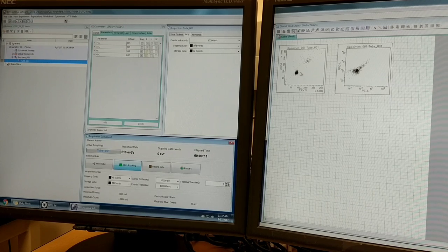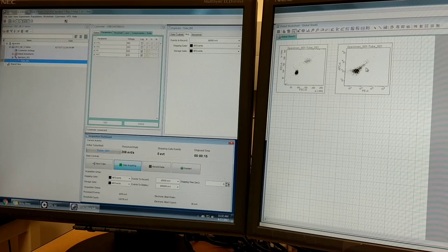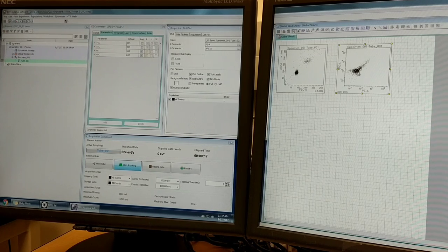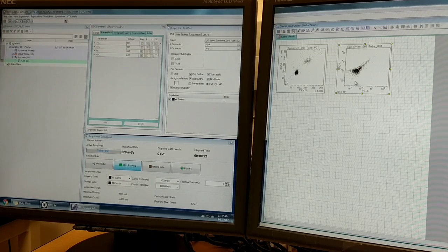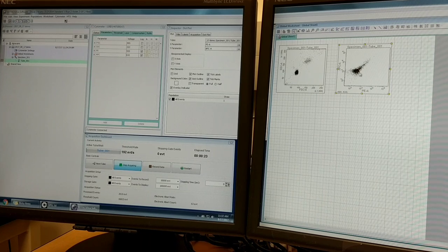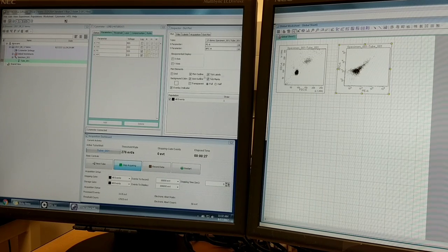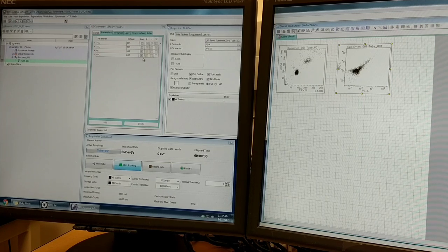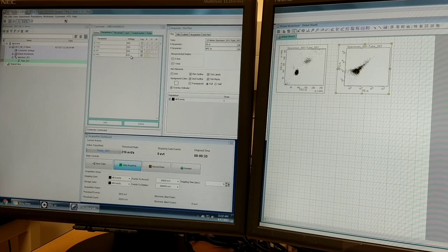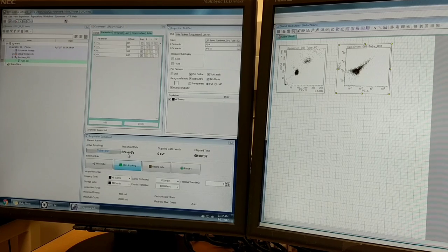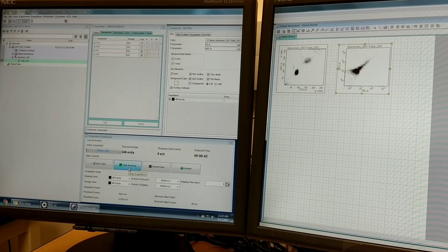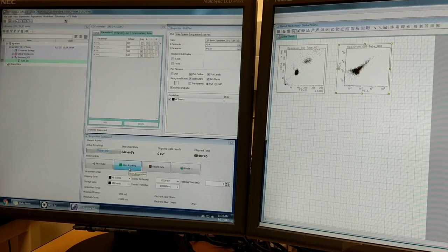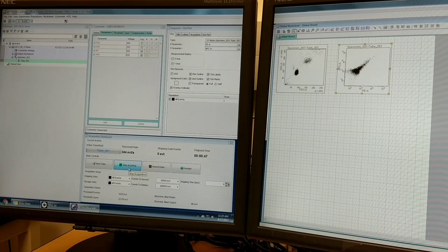Now that I have my forward and side scatter where I want them, I'm going to look at the fluorescent plots. I can already tell the background looks reasonably high, especially for APC, where I've got signal at 10 to the third for unlabeled beads. So I'm probably going to turn that down, but I usually don't turn that down based on unlabeled beads. Usually I turn that down based on the positive labeled beads, because you'll be able to see both the positive and negative population and get those exactly where you want when using your single stain controls.